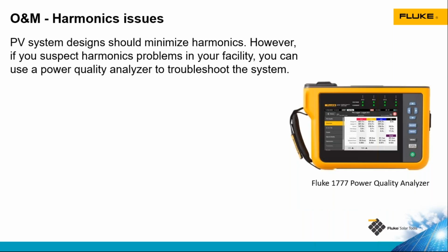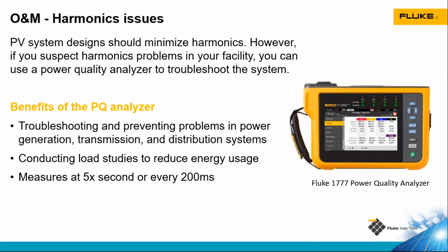We talked a bit about power quality and harmonics. We can use our power quality analyzers to find harmonic or voltage and frequency issues. Some of our power quality analyzers can also be used for load studies. So they can measure the power and energy consumed by a load, and we can use that information to properly size energy storage systems for backup power or resiliency purposes. When using that type of application, it's really important to know the power and energy draw of the loads so that we can size the energy storage system appropriately.